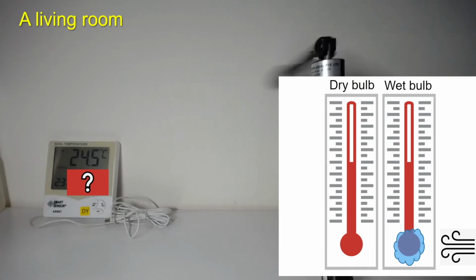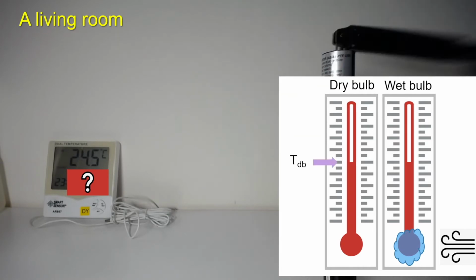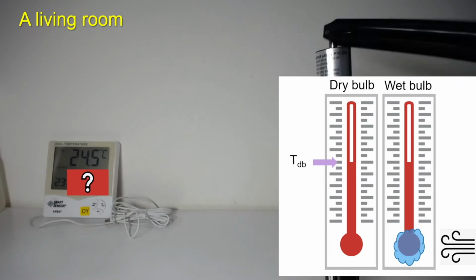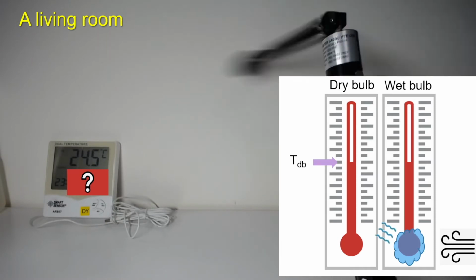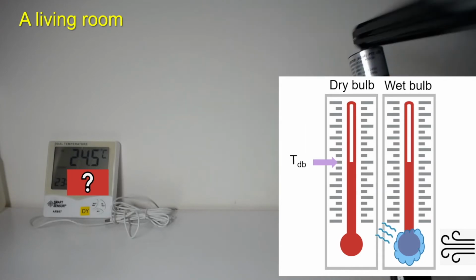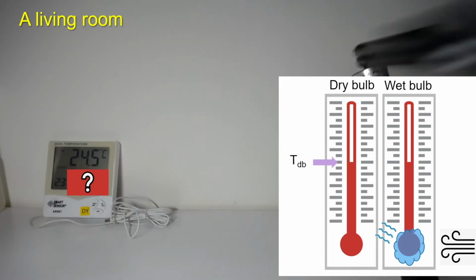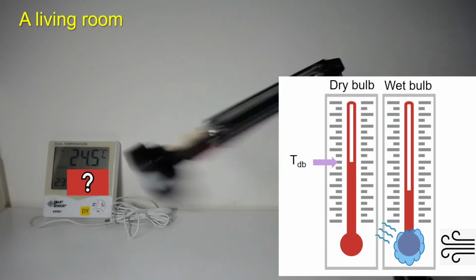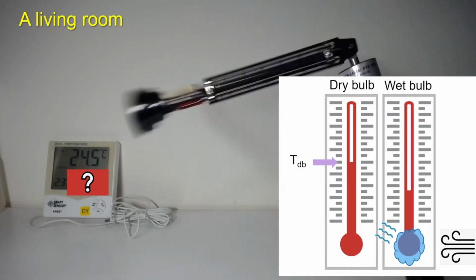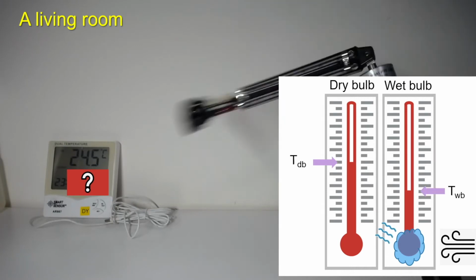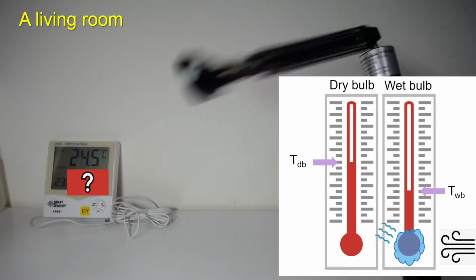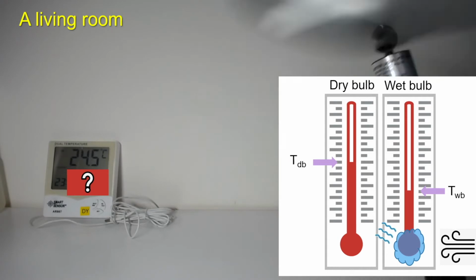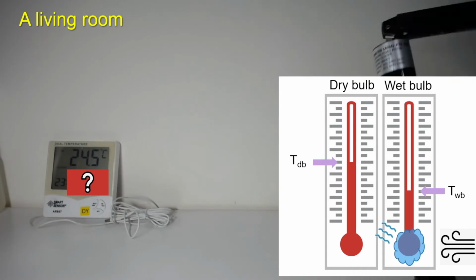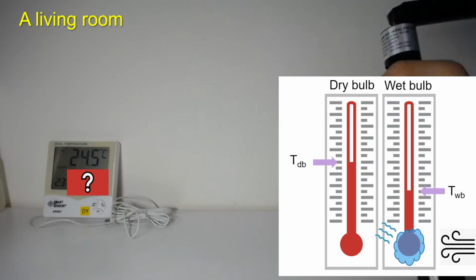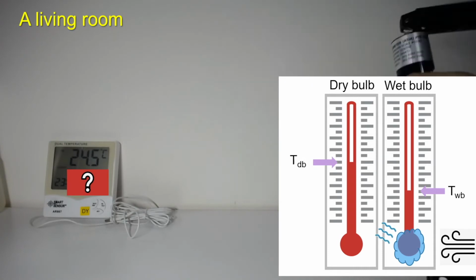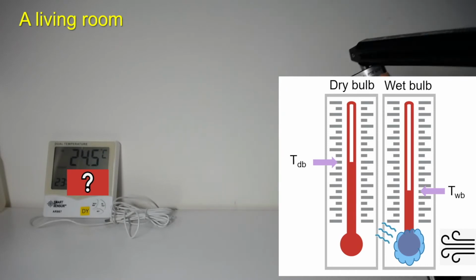The dry bulb thermometer will just measure the room temperature, called the dry bulb temperature. On the other hand, the water around the wet bulb thermometer will evaporate. During evaporation, heat is taken away, so the temperature of the thermometer will drop while humidity around it increases until saturation. And the corresponding temperature is called the wet bulb temperature. How much the temperature of the wet bulb will drop depends on the relative humidity of air. The lower the relative humidity, the larger the temperature difference. Therefore, we can measure the relative humidity from the difference in the two thermometer temperatures.